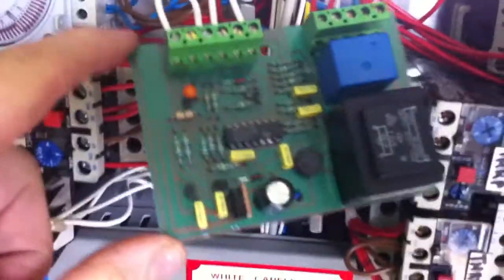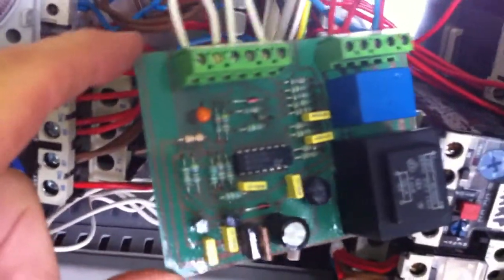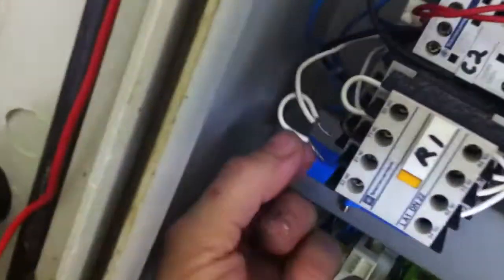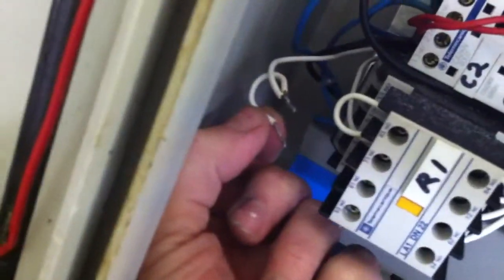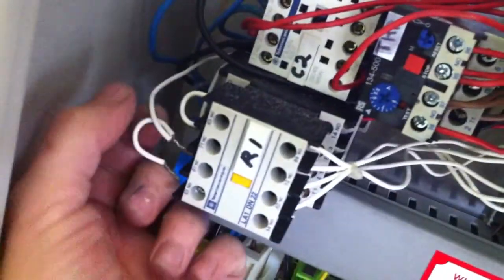This little control board was keeping the solenoid open when the probe was covered in ice, so it should have turned off. I'd even gone as far as disconnecting the probe here and it was still keeping it on.